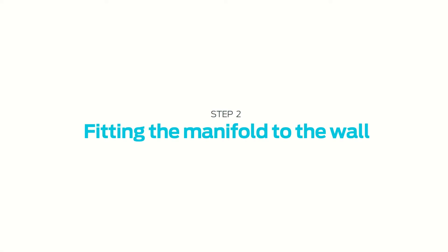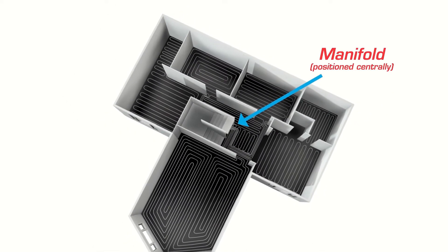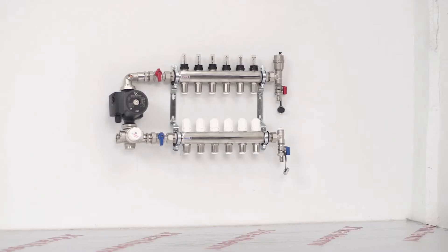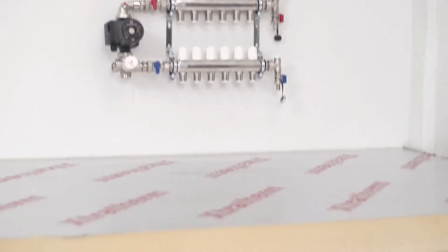Fitting the manifold to the wall. The manifold must be located as centrally as possible to the circuit it's feeding, allowing enough height to accommodate the installation and screed depth.